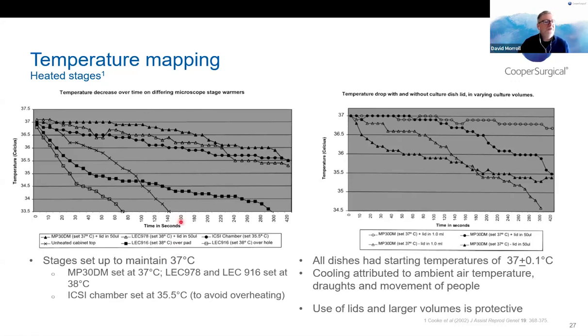And what you can see, it's a bit difficult for you to see all of the different symbols, but the take-home message from these is really that over the course of a couple of minutes, all of these dishes, they set up standard dishes at 37 degrees, put them on the heated stages, and they all lose temperature over time. So after 3 minutes, you can see that they're down at around 36 degrees or so. So what they noted was that cooling was affected by ambient air temperature. It was affected by draft, so airflow. And of course, airflow was also linked to movement of people. So if people are moving around, you're more likely to see cooling.